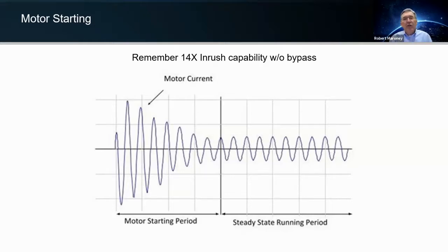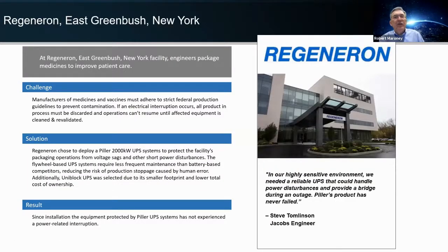It is, the motor is much more well suited for these types of robust requirements because of its ability to, A, deliver inrush current, and B, you have a lot of steel to dissipate the heat from that kind of rise in requirement. As you can show a motor here. Come on, there you go. A manufacturing site up in New York State. This is a fill plant for a pharmaceutical facility. Almost all motor drives in that facility. Many very large motors across the line starting in that particular application.